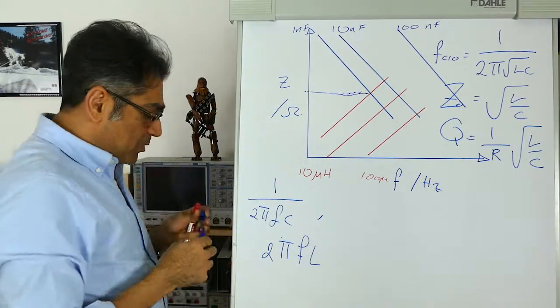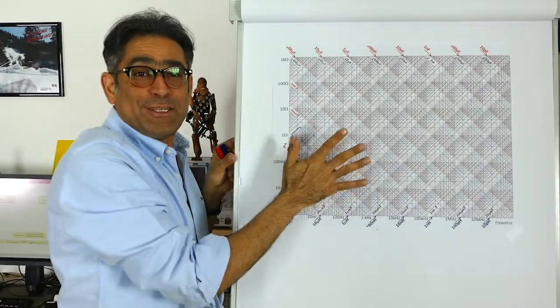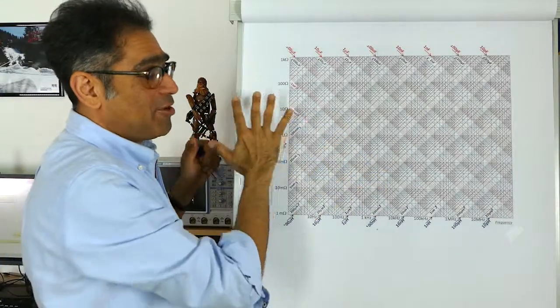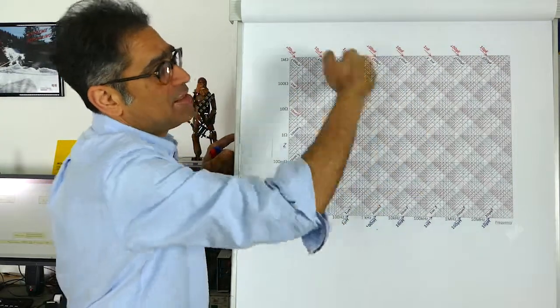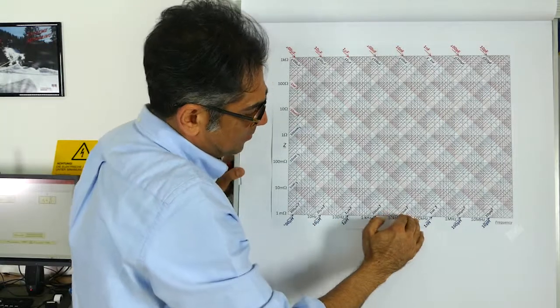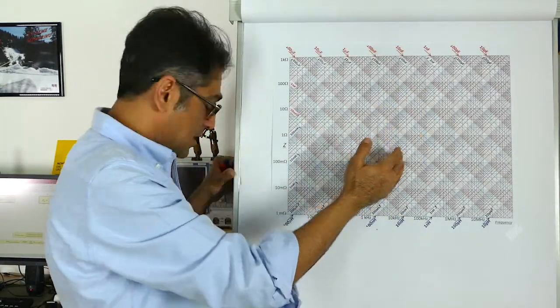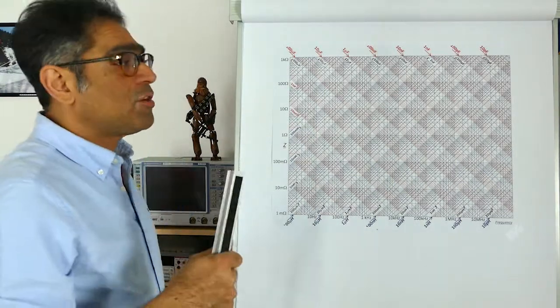When I plot all of these on top of each other it looks exactly like this. I know it looks a little intimidating to start with, but please don't be scared of this paper. What we have here is a series of capacitors showing how their impedances fall with frequency, and a series of inductances showing how their impedances rise with frequency. Now, let's say from our specification we know that the cutoff frequency of our differential mode filter is going to be 7 kHz.